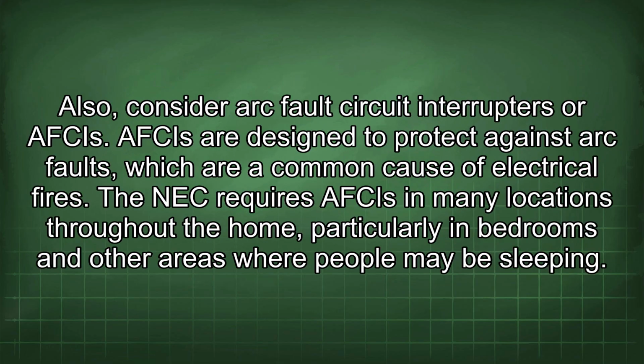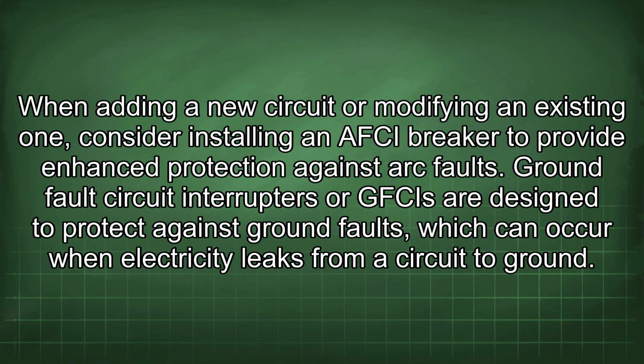Also, consider arc fault circuit interrupters, or AFCIs. AFCIs are designed to protect against arc faults, which are a common cause of electrical fires. The NEC requires AFCIs in many locations throughout the home, particularly in bedrooms and other areas where people may be sleeping. When adding a new circuit or modifying an existing one, consider installing an AFCI breaker to provide enhanced protection against arc faults.